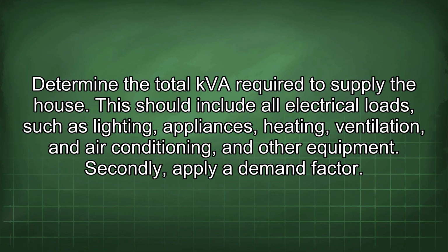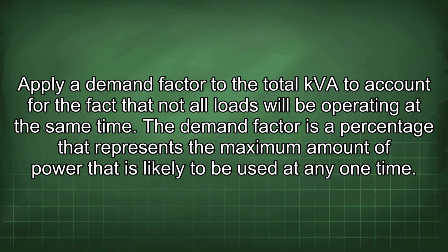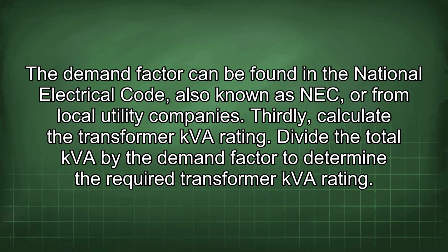Secondly, apply a demand factor. Apply a demand factor to the total kVA to account for the fact that not all loads will be operating at the same time. The demand factor is a percentage that represents the maximum amount of power that is likely to be used at any one time. The demand factor can be found in the National Electrical Code, also known as NEC, or from local utility companies.